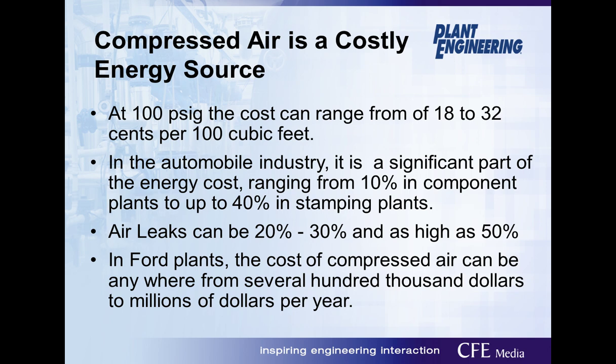So as an example, at 100 PSI, that can range anywhere from 18 to 32 cents. That should say per 1,000 cubic feet. I apologize, this must not have been the updated one, but we'll get that changed before it goes online. But that's per 1,000 cubic feet of compressed air. And again, it depends on whether it's air-cooled or water-cooled.